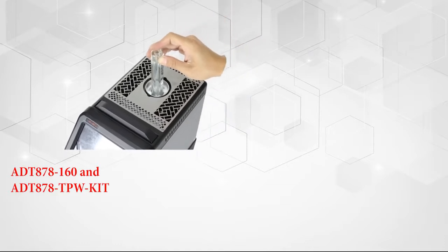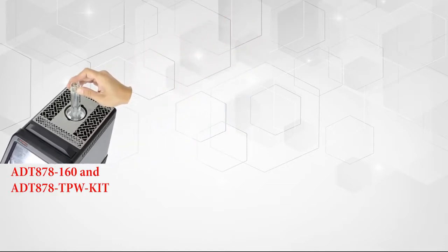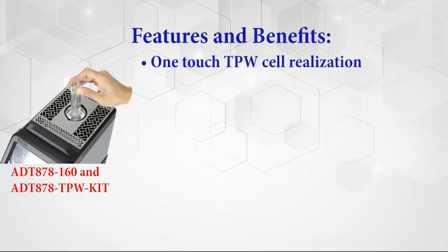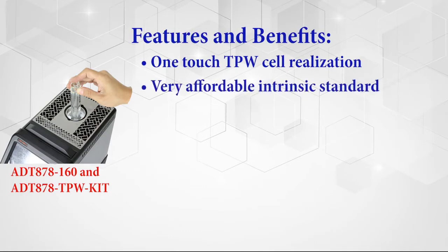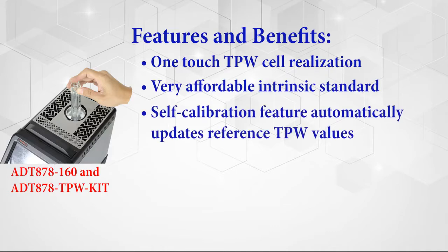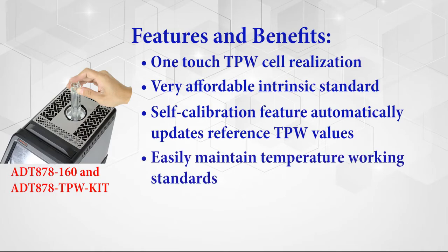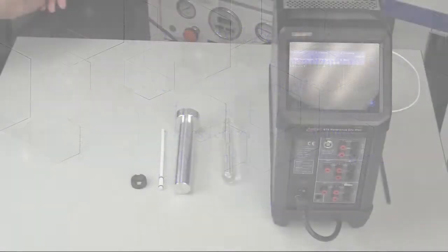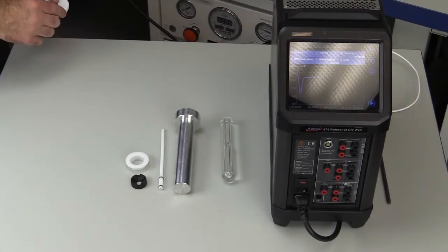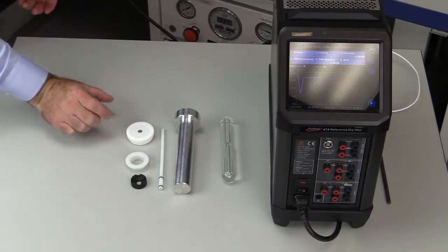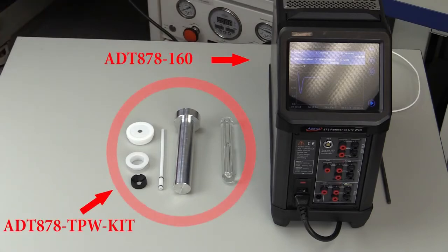ADT makes realizing the triple point of water a snap with the ADT878-160 reference dry well calibrator and the TPW kit by providing the following: a one-touch triple point of water cell realization, a highly affordable intrinsic standard, a self-calibration feature that automatically updates reference probe TPW values, easily maintained temperature working standards, and is fully self-contained. To begin, you will need the ADT878-160 reference dry well calibrator and ADT's triple point of water kit.